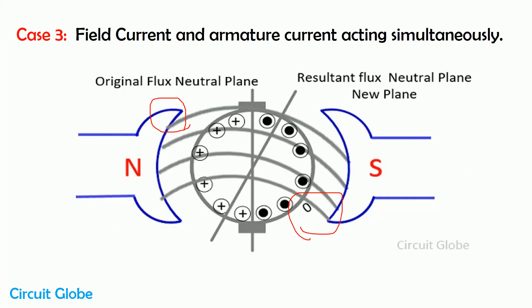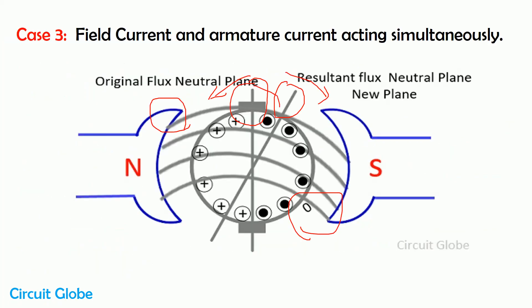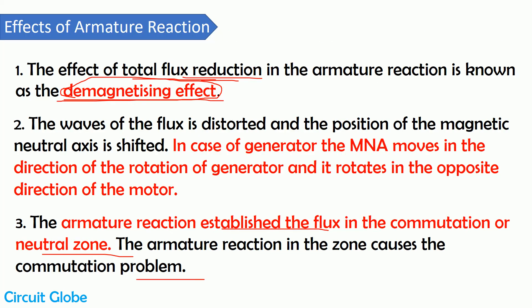Because of armature reaction, the magnetic neutral axis of the machine may get shifted. This magnetic neutral axis turns in the direction of machine rotation in case of a generator, and in the opposite direction in case of a motor. Also, the armature reaction establishes flux in the commutation or neutral zone of the machine. Since there is no EMF in the neutral zone and we place brushes there, the flux induced by armature reaction in that axis means the brushes may get damaged. These are the main effects of armature reaction on the machines.